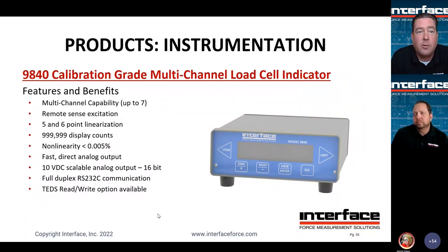All right, instrumentation side. So 9840, this is a very popular device used in many hundreds of calibration labs worldwide, really, at this point. A lot of really good features. Many people may not know this, but we are not limited just to a single or a dual channel configuration anymore. We've done up to 7 at this point in time. This has a lot of great features on it. Remote sense excitation, again reducing any potential error due to a voltage drop across the cable run. This does point-to-point linearization in either 5-point or 6-point.